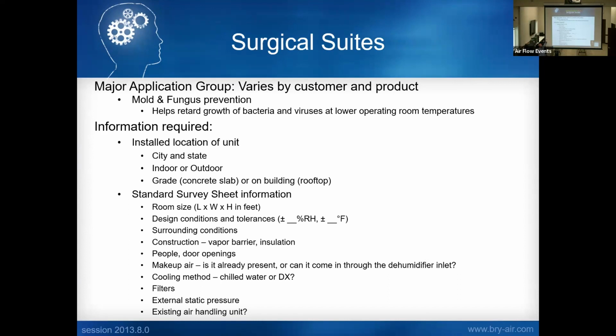In most applications, we need to know the city, the state, whether the unit is indoor or outdoor, and if outdoor, whether it's on the grade or on the roof. You typically need to know the size of the room. I've seen this a lot: we deal with cubic feet, the volume of the room. A lot of people just say, "I've got 5,000 square feet, can you dehumidify it?" Well, an 8-foot height versus a 20-foot height are two different things. So we need to know the volume of the room, the design conditions, tolerances, and surrounding conditions.